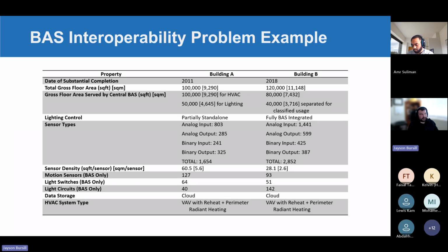So we ended up in a problem with this because we couldn't actually take the occupancy sensors, the passive infrareds attached to the lighting system, and feed that data directly into the automation system. So we had to have some sensor redundancy to get the occupancy data from the spaces. This became tricky and frustrating, and cost a fair bit of money to duplicate the sensing capability. In some cases, we even had to put in standalone sensors for research purposes.